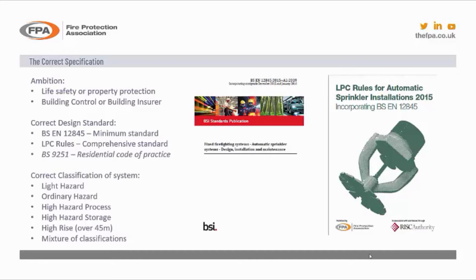Ordinary hazard, well, this is split into 4 areas. We've got ordinary hazard group 1, ordinary hazard group 2, 3 and 4. So an ordinary hazard group 1 risk could be a hotel, a school or a hospital. An ordinary hazard 2 risk could be a museum, a bakery or an abattoir. Ordinary hazard 3, which is probably the most common, we're talking department stores, so your shopping centres, office tower blocks, plant rooms. And ordinary hazard group 4, cinemas, theatres, cotton mills.